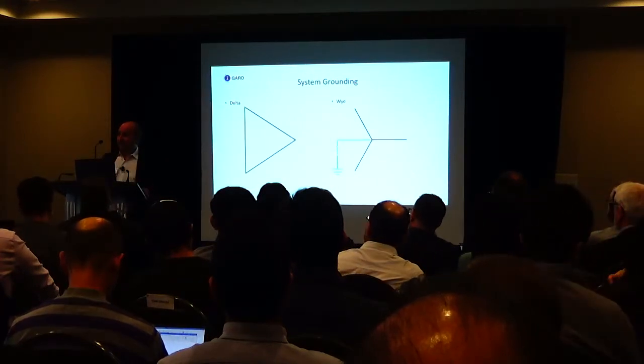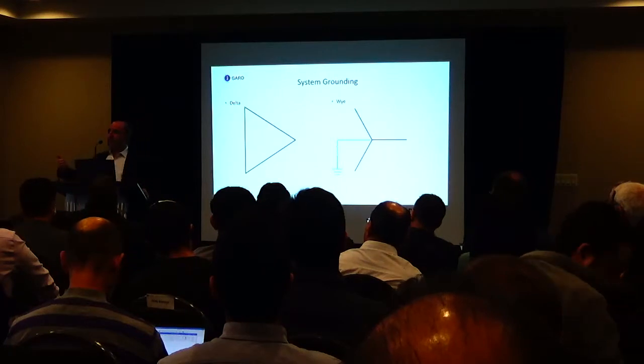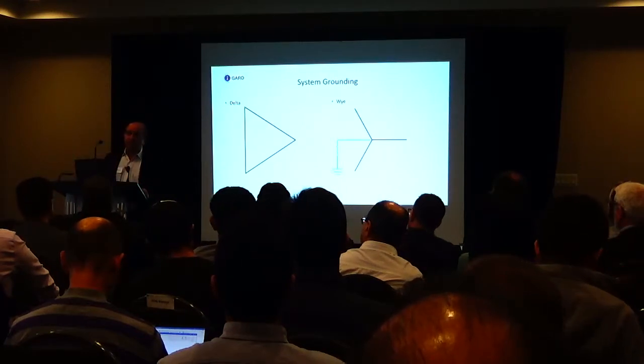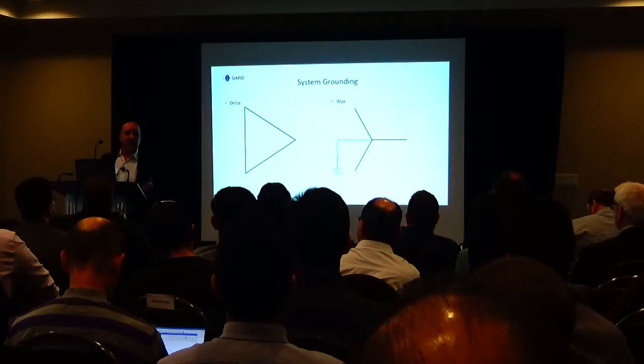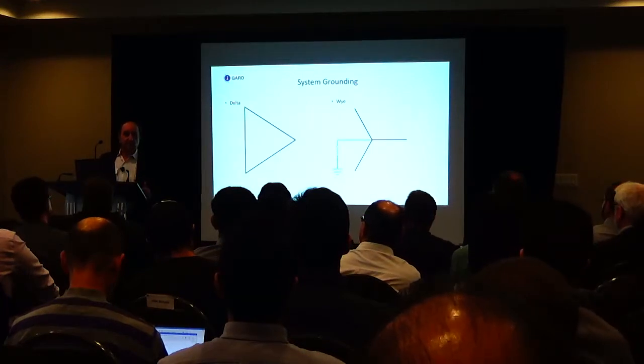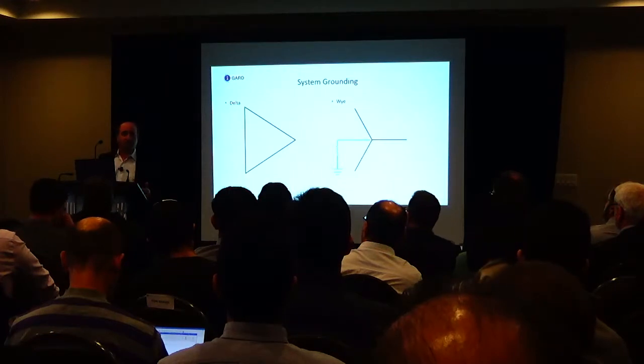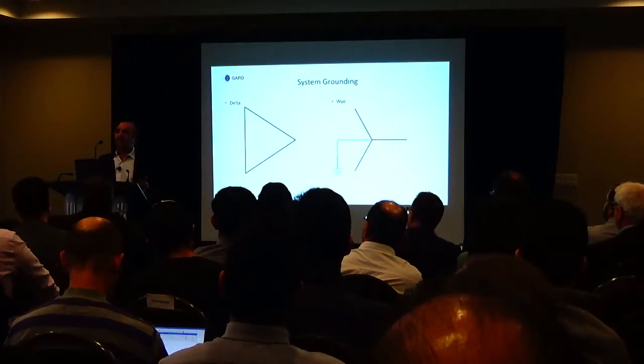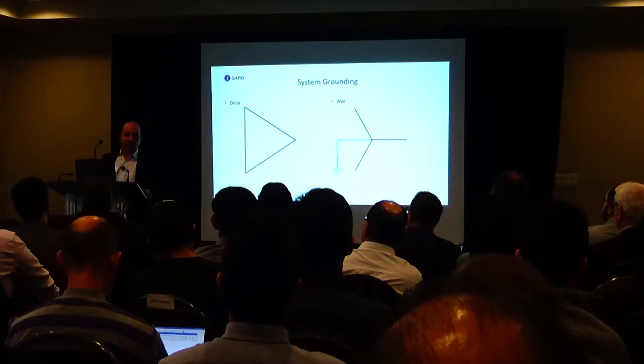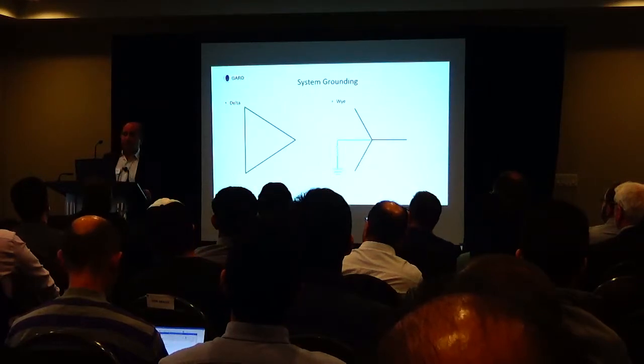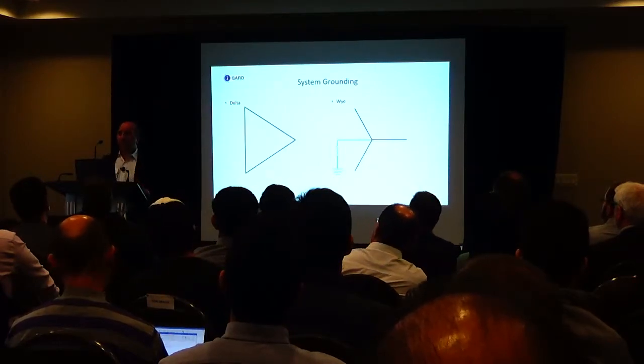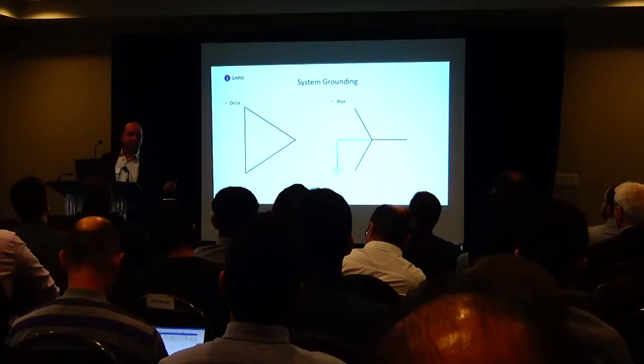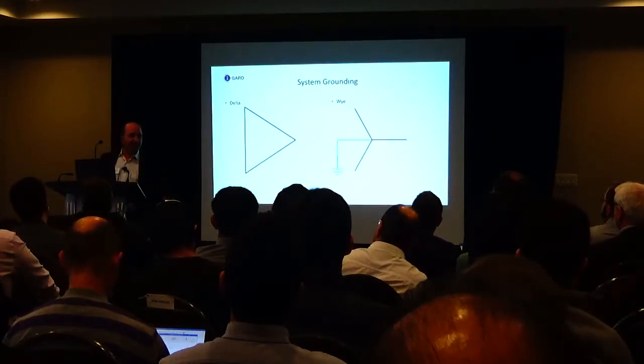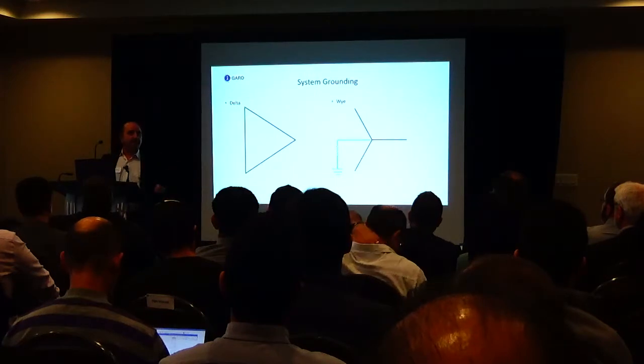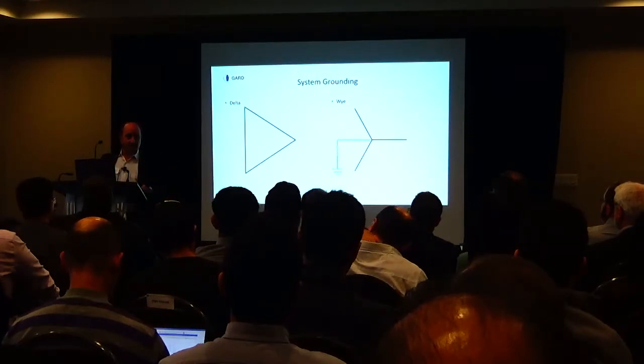So you have increased productivity because the most typical fault that you're going to have in an electrical facility is a single phase to ground fault. Who has ever seen a 3-phase fault occur all by itself? Nobody. It's rare that you have a 3-phase bolted fault. Although we have to rate all of our equipment for 3-phase bolted faults, they're very rare in occurrence. Most faults begin as single phase to ground faults, and they propagate to a phase-to-phase or a 3-phase fault.